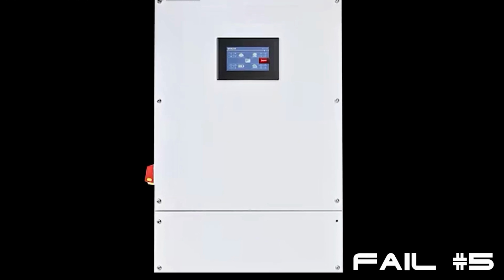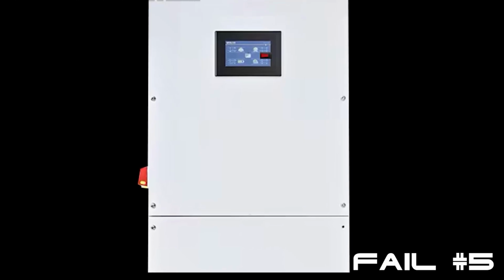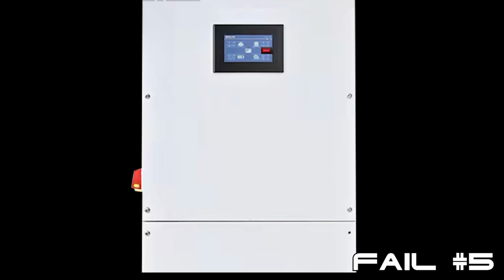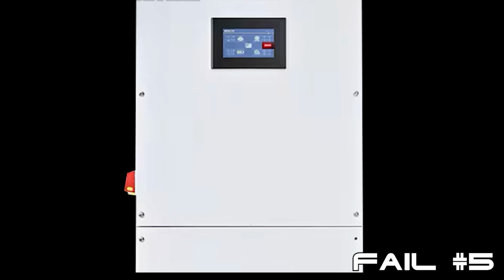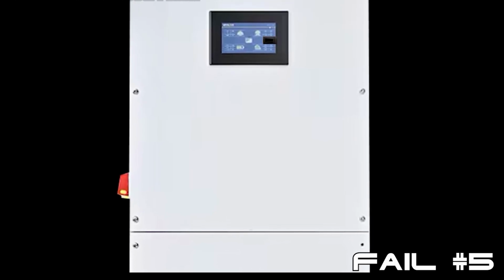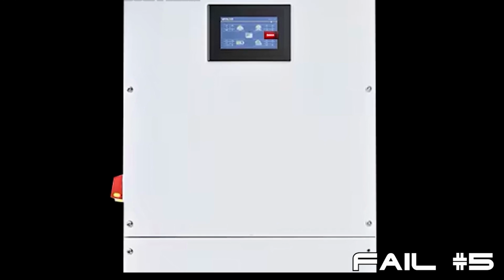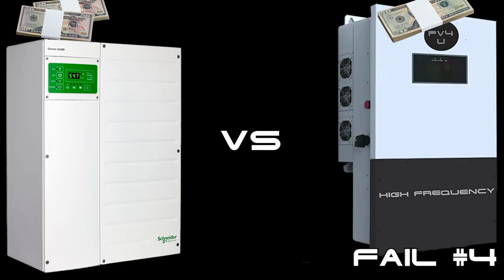Fail number 5. If you were expecting or are in need of a quieter inverter, then you should avoid a high-frequency inverter. Because high-frequency inverters operate at a much higher switching speed, when under load, they require much more aggressive cooling measures, which translates into multiple, noisy, high-speed cooling fans. While low-frequency inverters do produce some fan noise, the sound is nowhere near the level of a high-frequency inverter. Fail number 4. When it came to pricing, high-frequency inverters used to have an edge over low-frequency inverters. But now, because of technological advancements and more competition entering the market, despite the major differences in performance, safety, and reliability, the price difference between these two technologies has substantially narrowed to just a few dollars. From a financial perspective, it simply no longer makes sense to purchase a high-frequency transformerless inverter.